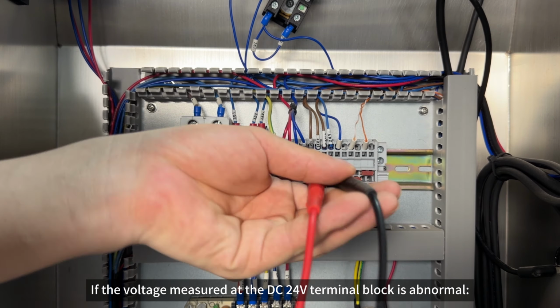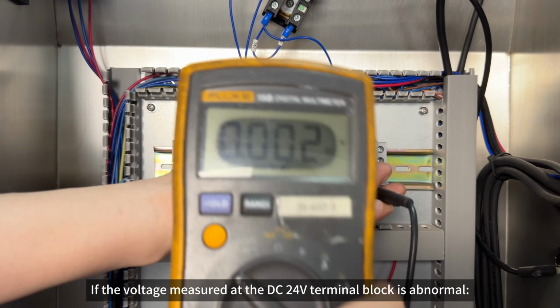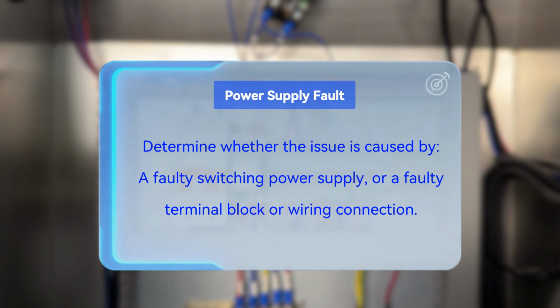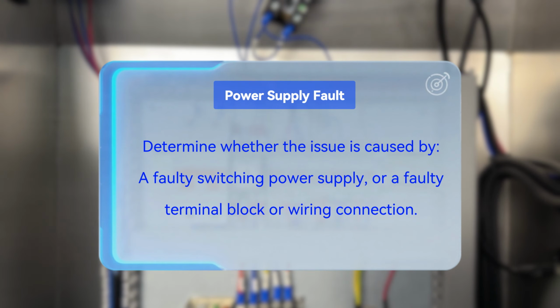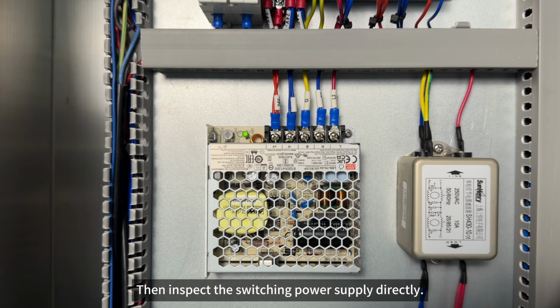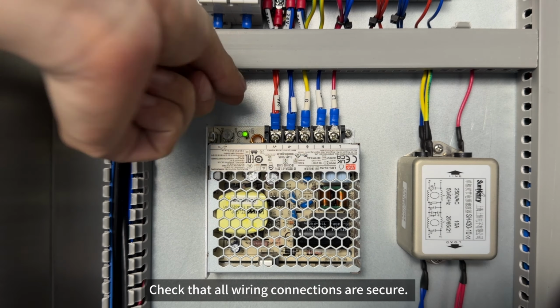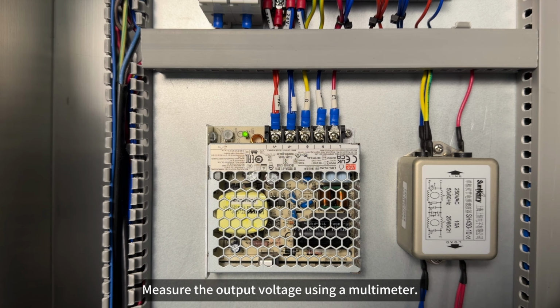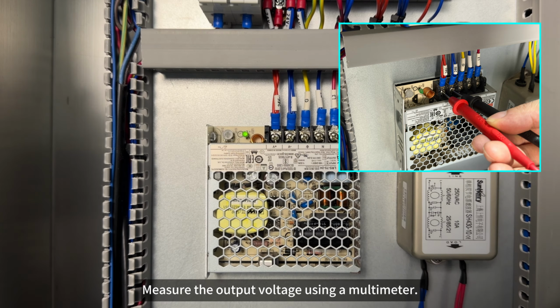If the voltage measured at the DC 24 volts terminal block is abnormal, determine whether the issue is caused by a faulty switching power supply or a faulty terminal block or wiring connection. Then inspect the switching power supply directly. Check that all wiring connections are secure. Measure the output voltage using a multimeter.